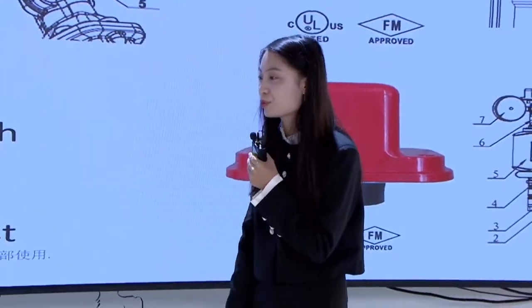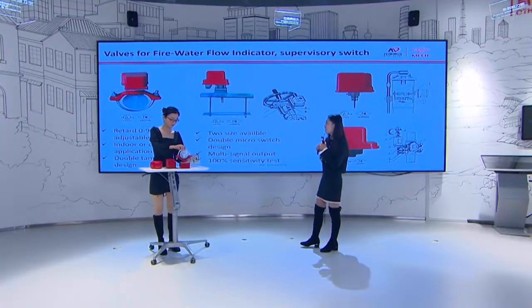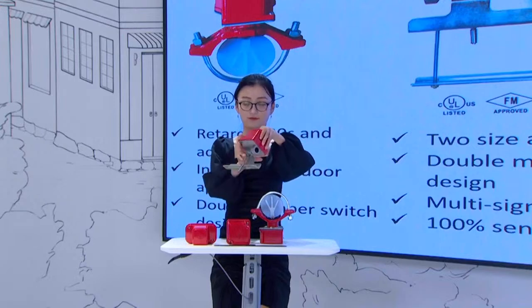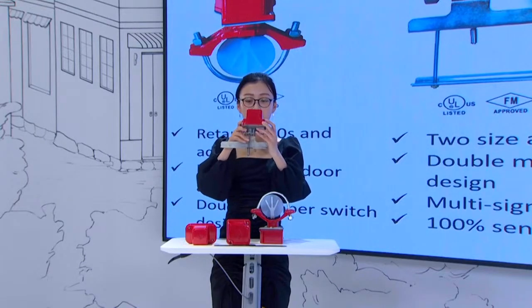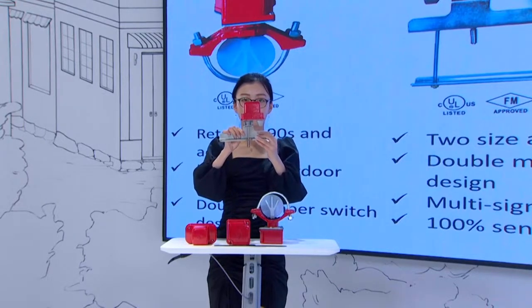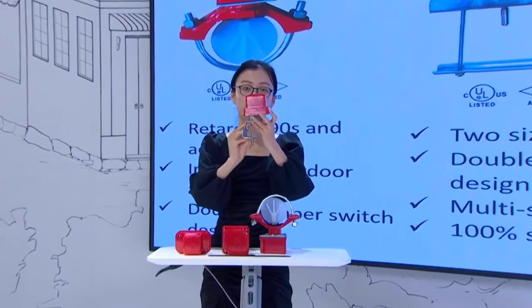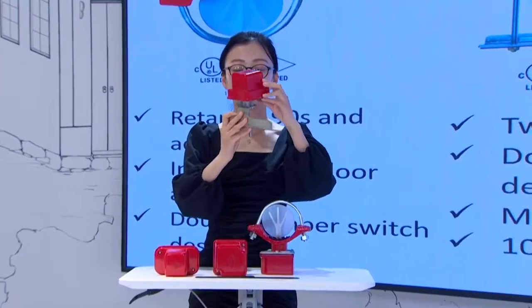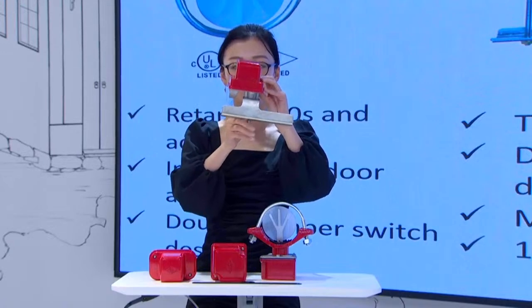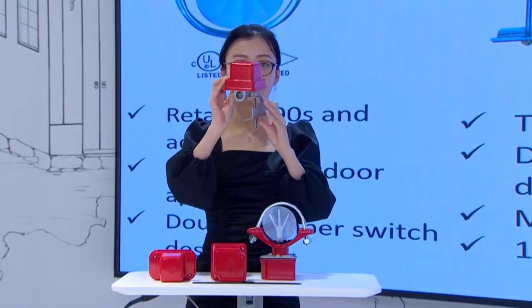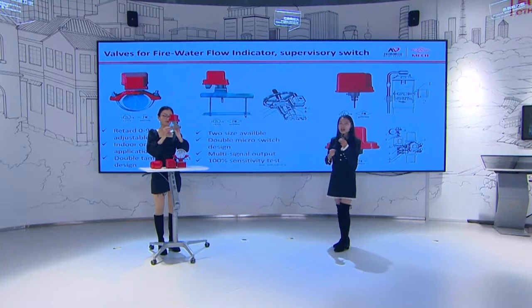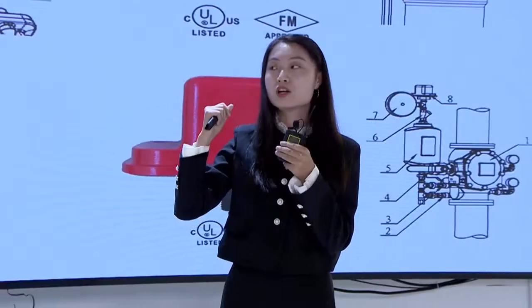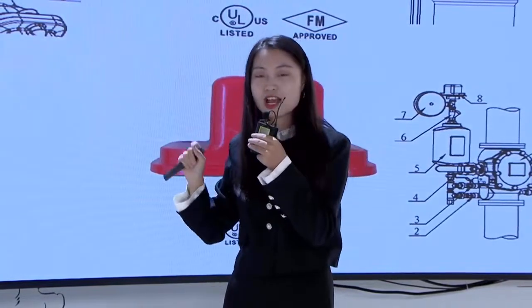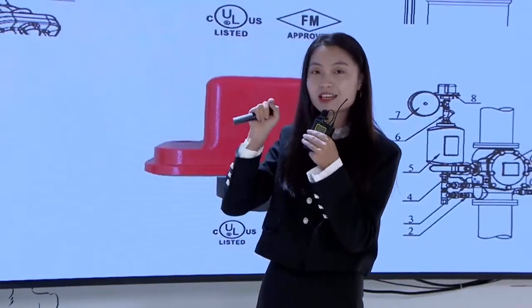And the next item we want to introduce is our supervisory switch. And this product is used to monitor the opening position of OS&Y gate valve for the fire protection system. And for this product, we have two sizes available. One is for gate valve from 2 inch to 16 inch, and the other is for the 18 inch to 24 inch.